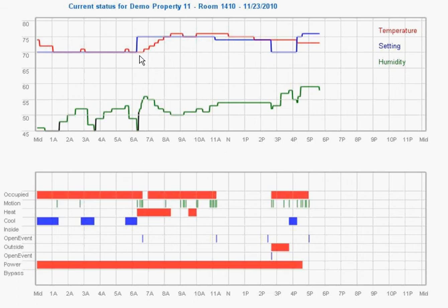Because the guest increased the temperature at 6:30 in the morning, asking for the room to be warmer, as you can see by this line here, the thermostat, which had been in cool mode to keep it down to 70 degrees, then changed into heat mode to be able to respond to the guest's request to raise the temperature in the room, and remained in heat mode until a little after 8:30, when the temperature appeared to be satisfied. And as you can see by this graph, the heat then turned off for a while.